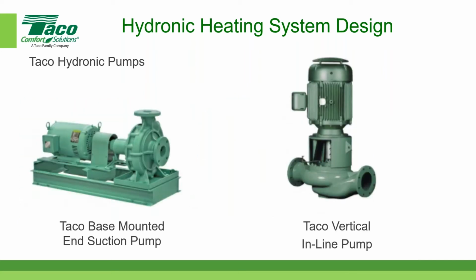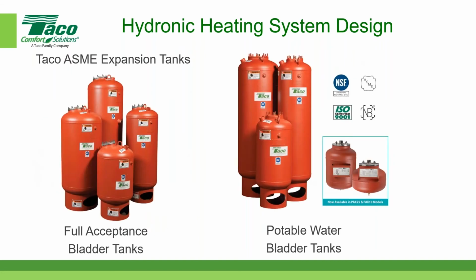The pumps are responsible for moving the fluid from the source, which in this case would be the boilers, to the terminal devices. The expansion tanks are responsible for, since the fluids that we're talking about in HVAC systems are basically water or water glycol solutions that are considered to be incompressible fluids, which means that as the temperature increases, the fluids will expand, and if they have no place to go, which is what the purpose of an expansion tank is, then it will break the equipment or the piping system.